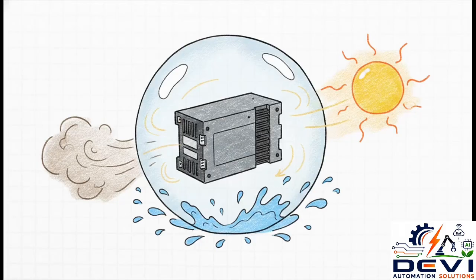Section 2. Site and Mechanical Setup. The crucial point here is managing the physical environment. The ideal location for your VFD has to be dry and dust-free to protect the internal circuitry. It also needs to be well ventilated to manage the ambient temperature and humidity. And you've got to keep it in a vibration-free area strictly away from direct sunlight. Heat is a VFD's worst enemy.